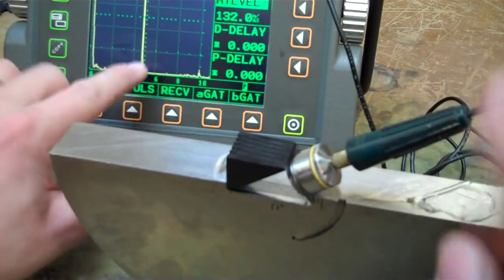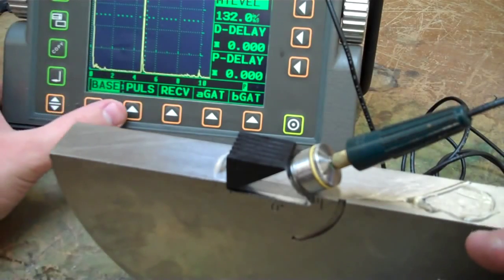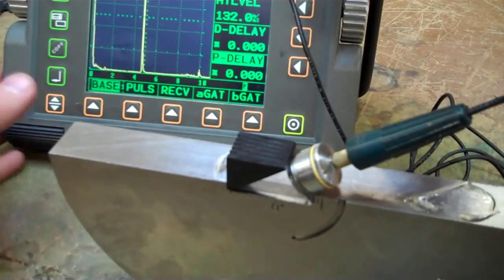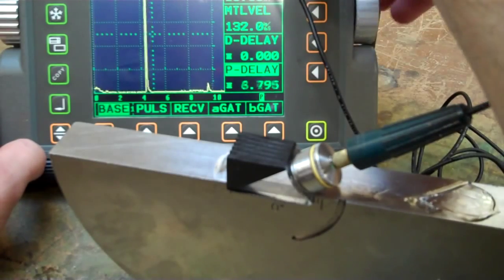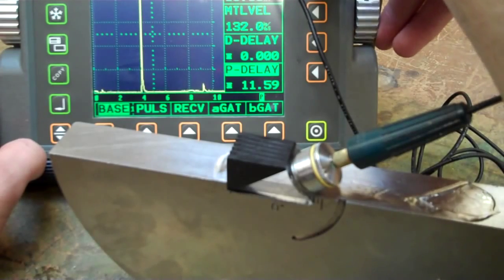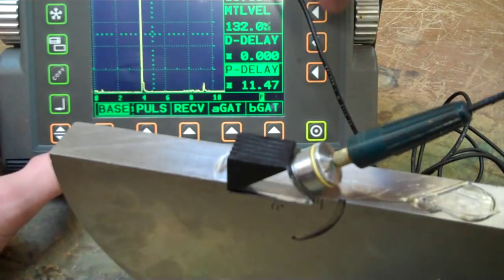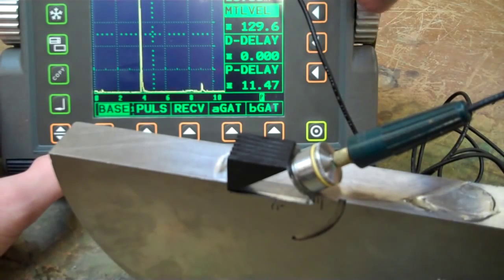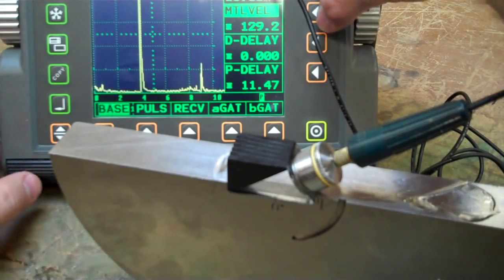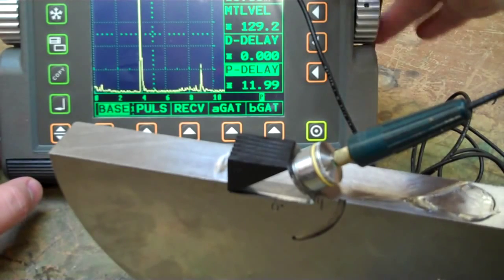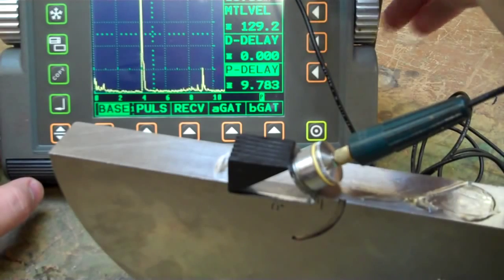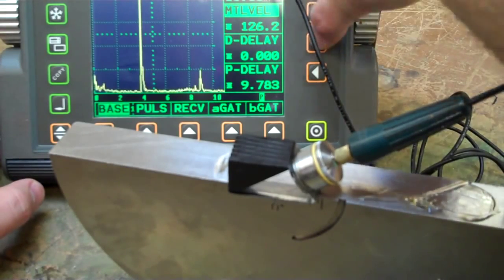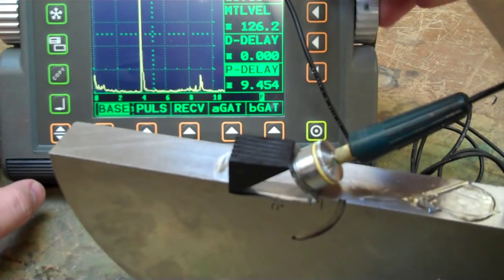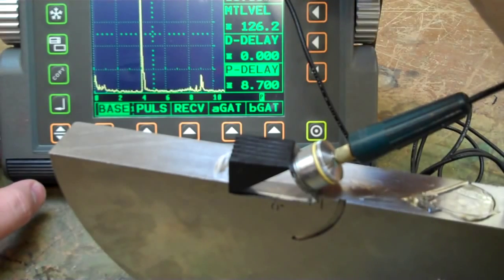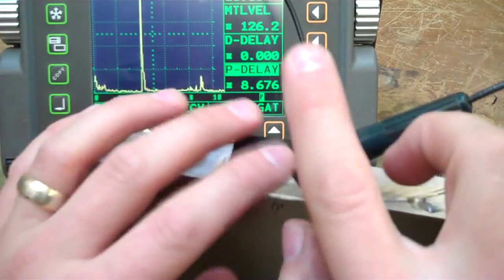Give it a little gain here. Here's our 4-inch signal, here's our 9-inch signal. We're not quite where we need to be. So now we go to our probe delay. Let's turn the scope a little bit to where that's at 4 inches. Okay, there's 4 inches. And we're pretty close to 9, but not perfect. So I'm going to try and make that as perfect as possible. Give it a little gain. Move our delay back. Alright. Keep coming in just a little bit more. Alright. That looks pretty close, 4 and 9. I would say so. Peaked up, looks good.